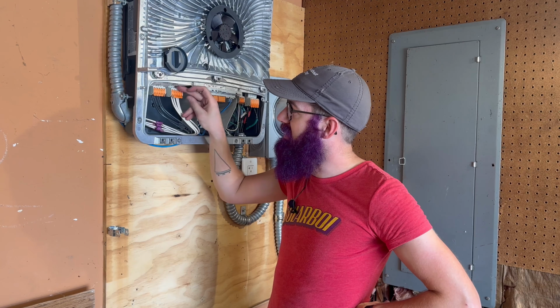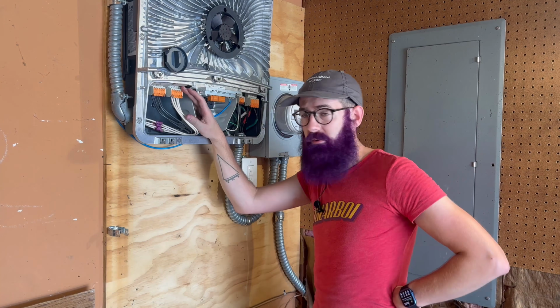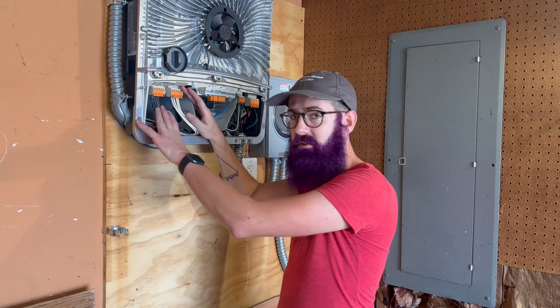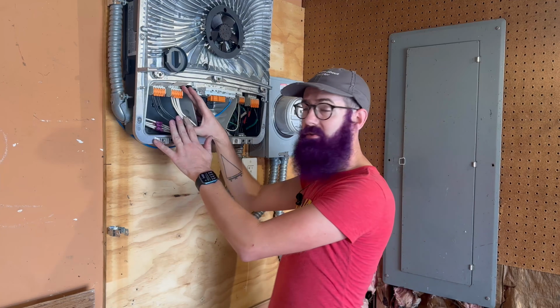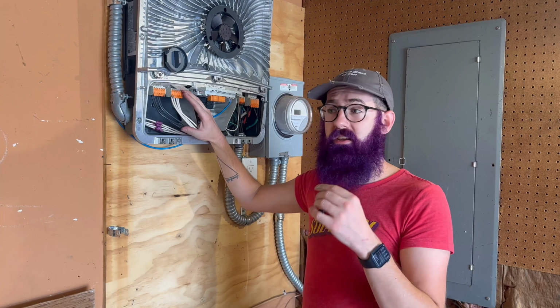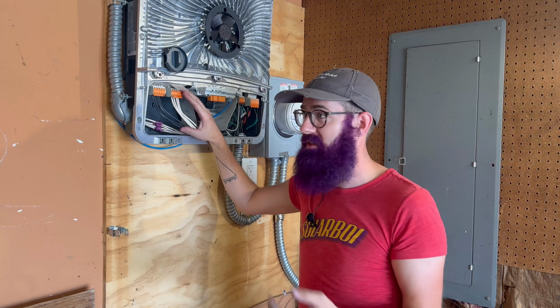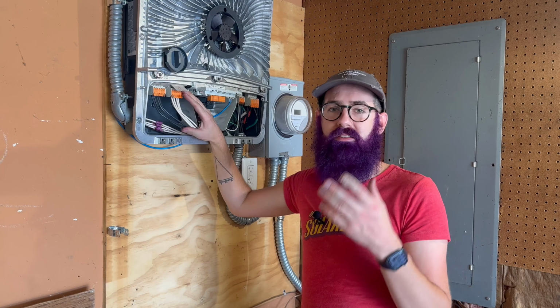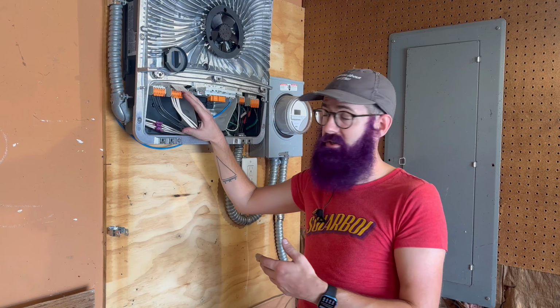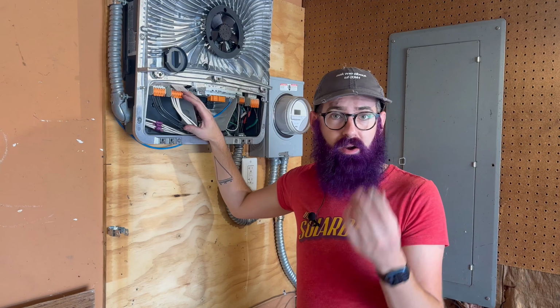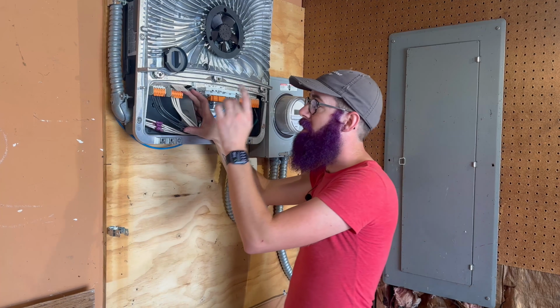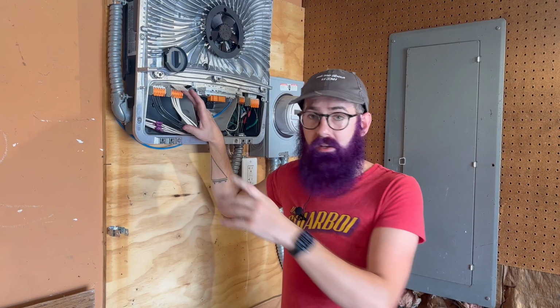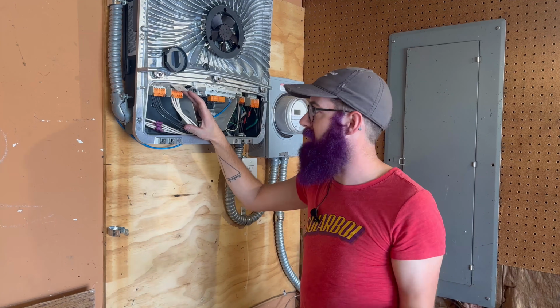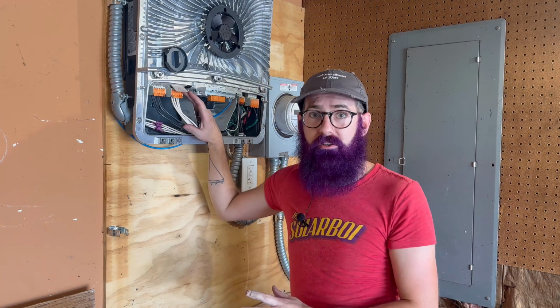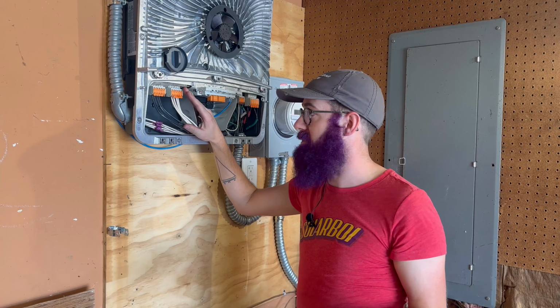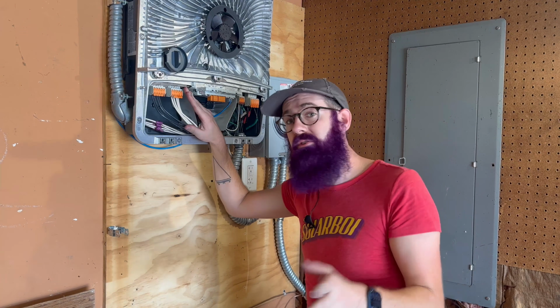You might be noticing here, if you are fairly new to the solar industry, that we have black wires and we have white wires. This was how solar installations used to be done. They used to be grounded systems. And what that referred to is basically the inverters at the time used transformers. And transformers needed to have a reference to ground, so they would ground one, either the positive or the negative, so that they could operate correctly. These days, it's all done in electronics and you don't need that ground connection anymore. So it's an ungrounded system.